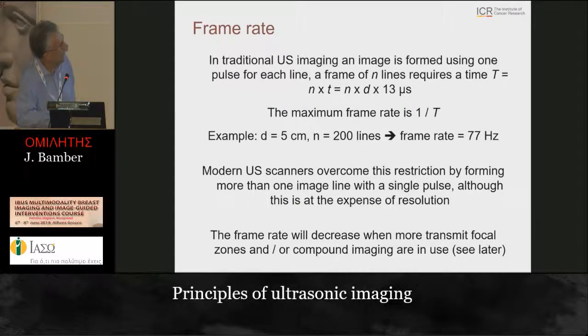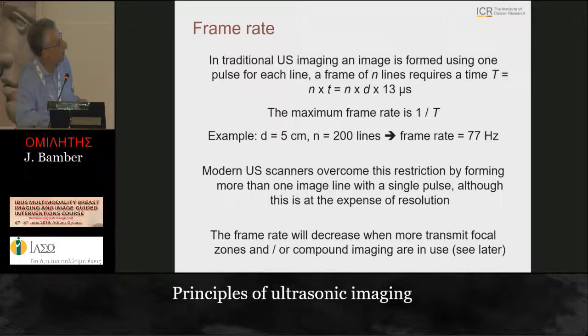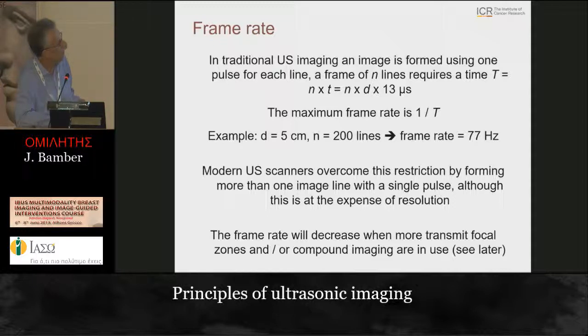The time to wait for one image line is the depth D multiplied by 13 microseconds, if D is in centimeters. We then multiply by the number of lines in the image to get the total frame time. The frame rate is the reciprocal of that. As an example: five centimeters depth, 200 lines, gives a frame rate of 77 Hertz.